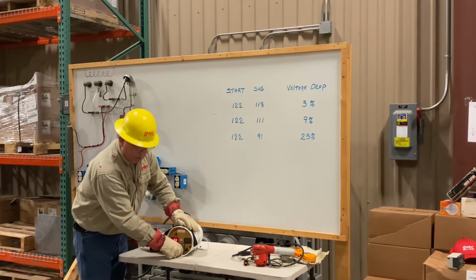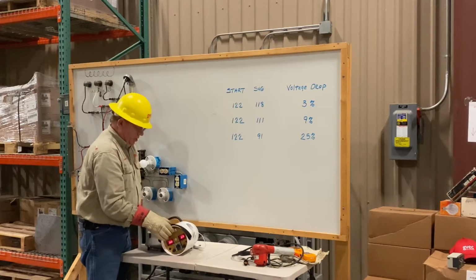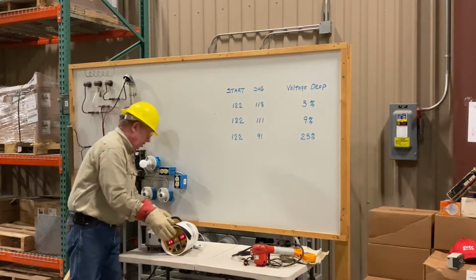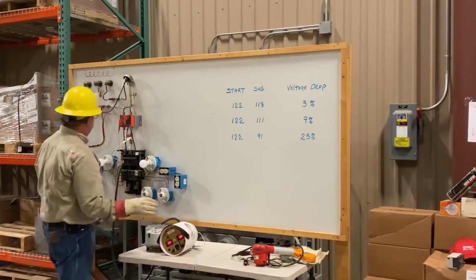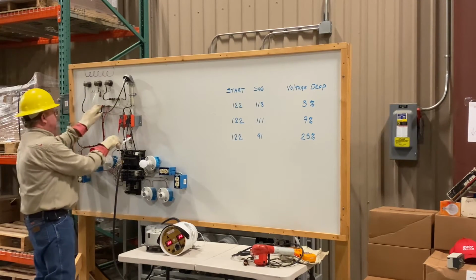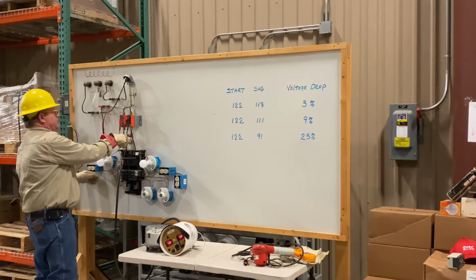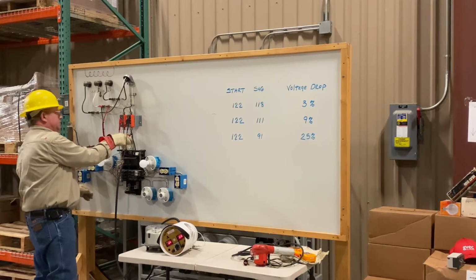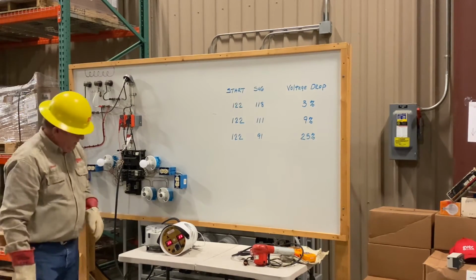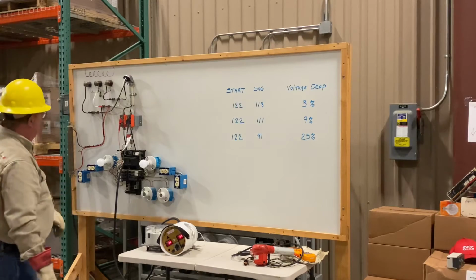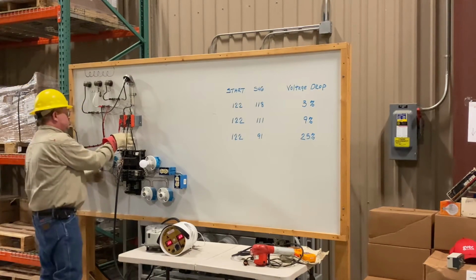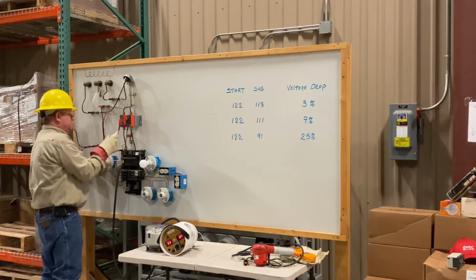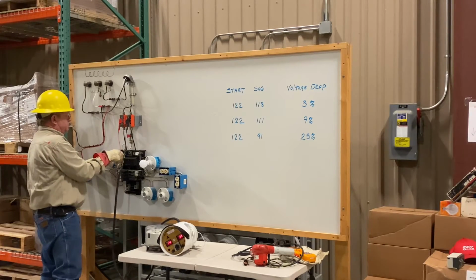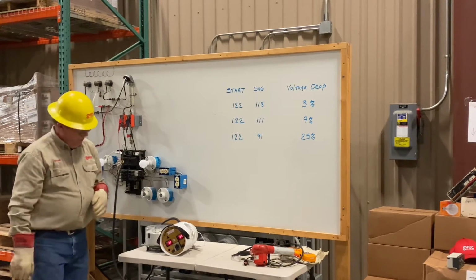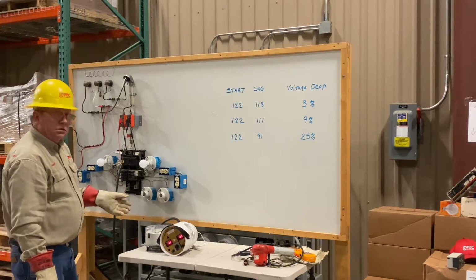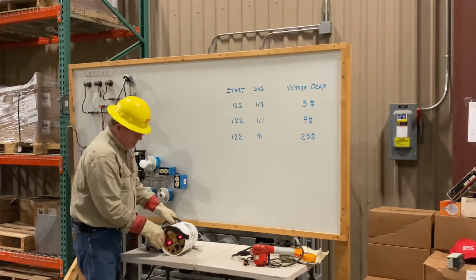We have an open neutral. That means I didn't do a good job putting it together. It came off the clip. Something happened. And usually it's the way that this got connected. See if our voltages are balanced. They're still trash. Come down here and get on this neutral load. Voltages are balanced. So the neutral connection is really, really important.